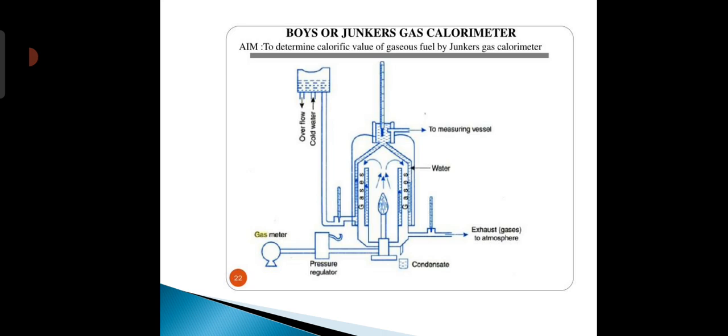See the first diagram of this Boys gas calorimeter. In this calorimeter there are two thermometers. First is T1 that determines the temperature of incoming water, and second thermometer T2 that determines the temperature of outgoing water. Next is the pressure regulator, condenser, exhaust gases, and the gas meter.